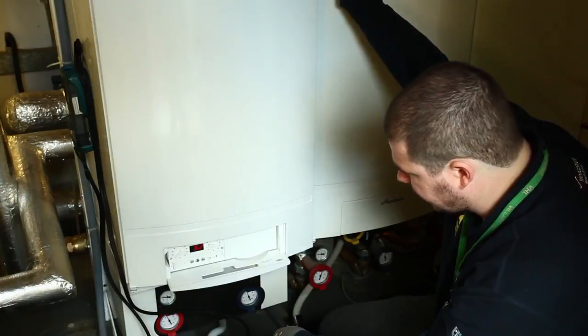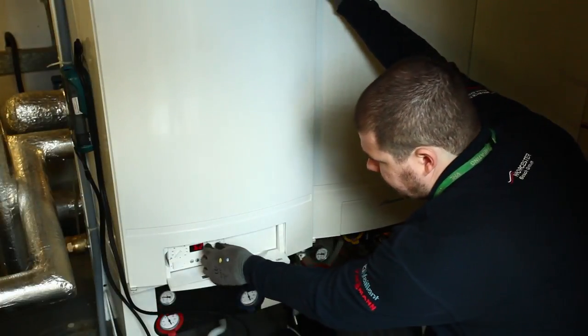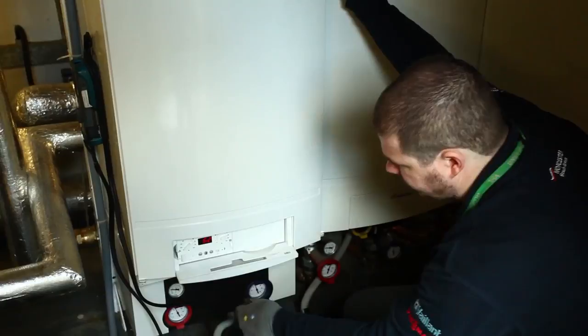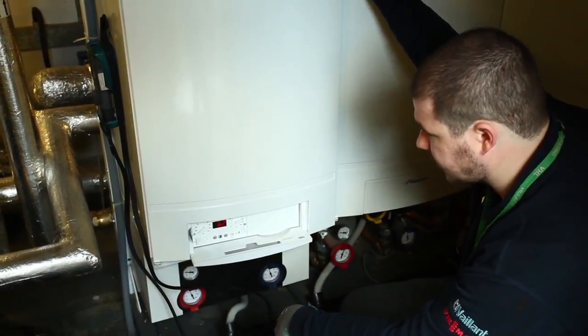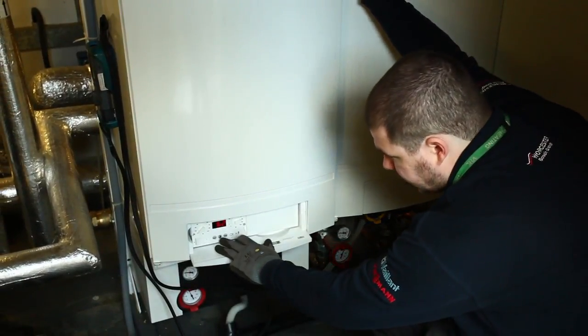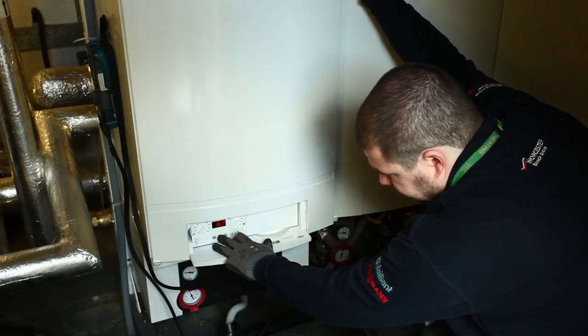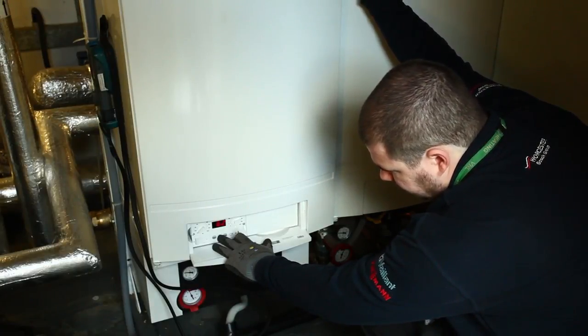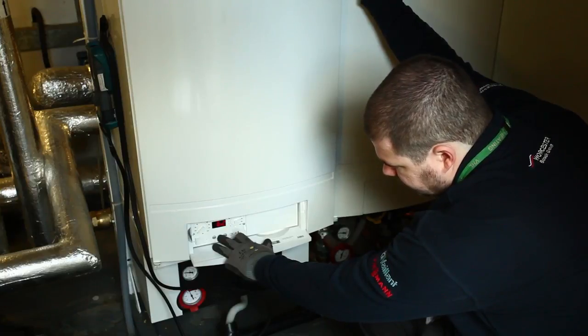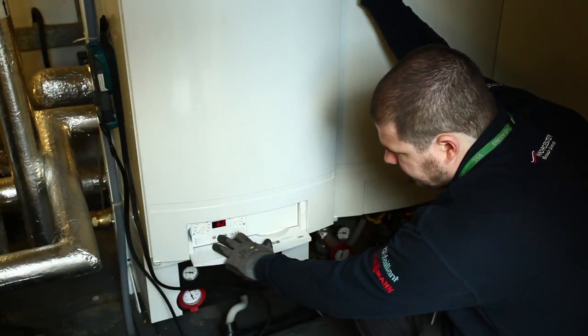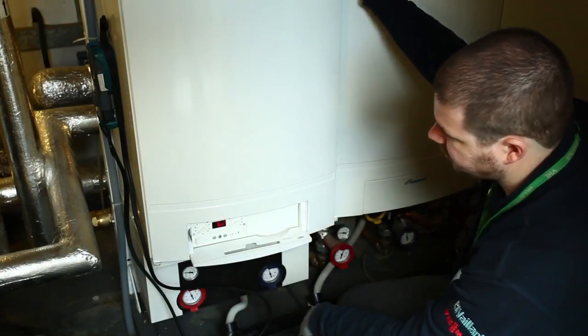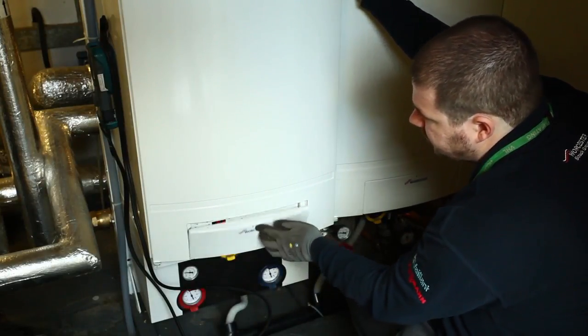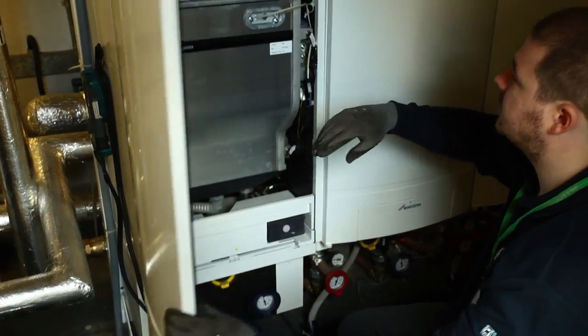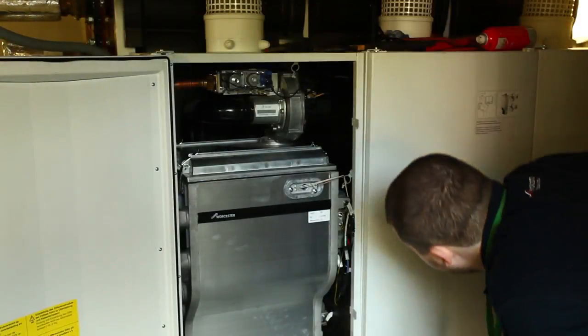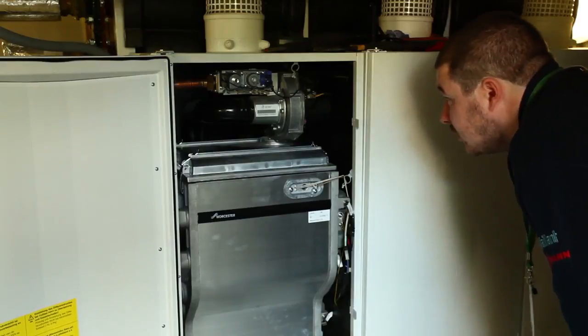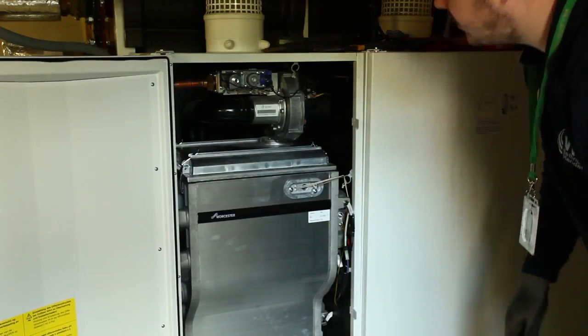Okay, after we've completed our service and our check with the initial commissioning, we set our temperature to about 80 or 90 degrees, only briefly for servicing and commissioning. We hold the centre button for 5 seconds and this engages the service mode on the boiler, which we would test the high flame and the low flame and the condition of the combustion. When the red light begins to flash, it then begins the ignition sequence. So we just check to make sure that we've got a nice even flame, it's burning lovely and blue, and after that we put the analyzer in.